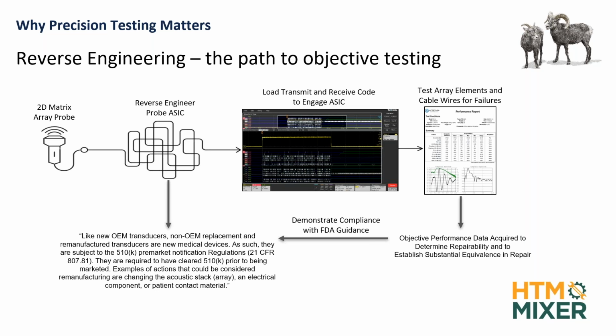The FDA says, like new OEM transducers, non-OEM replacement and remanufactured transducers are new medical devices. As such, they are subject to this. So we have two examples of action that could be considered remanufacturing: changing the acoustic stack, the array, or electrical component or patient contact material, because it's also subject to biocompatibility.